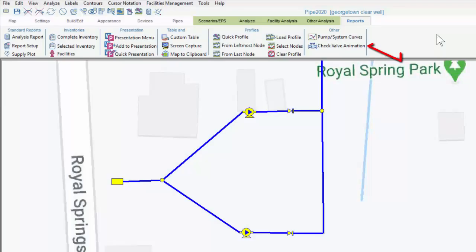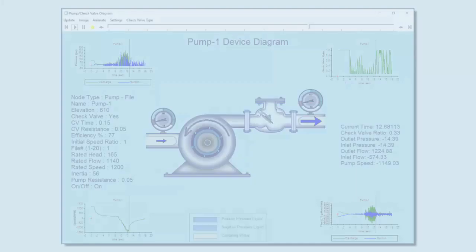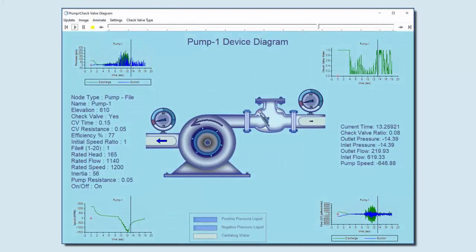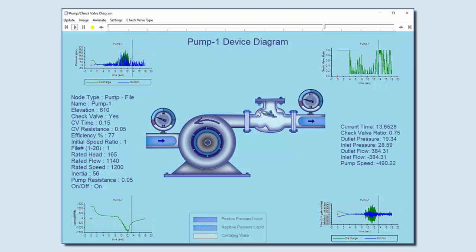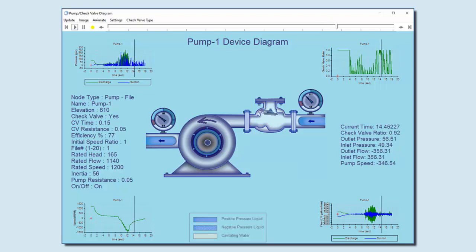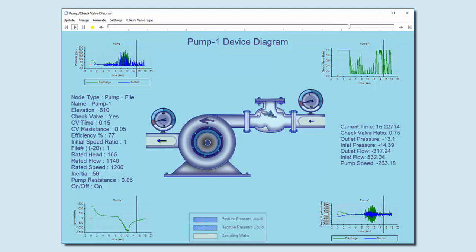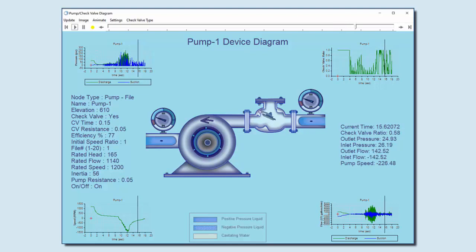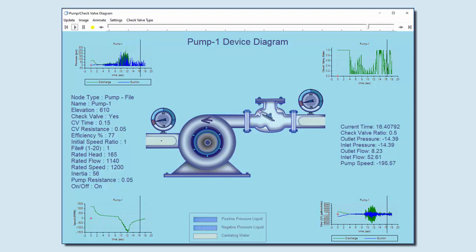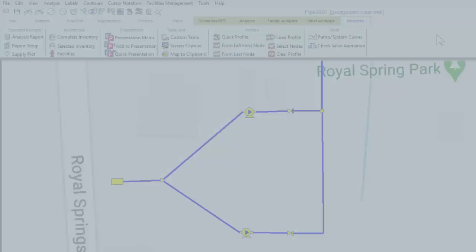We have a check valve animation feature, which shows the position of the check valve for pumps within the system, at any given case or time, within a KYPipe analysis. While it's helpful in KYPipe, this feature is especially useful for surge applications, since the position of the check valve can change rapidly, and displaying the check valve position allows us to diagnose a phenomenon known as check valve chatter.